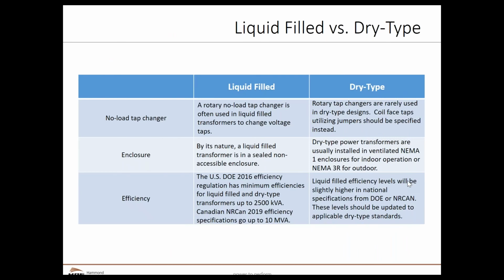So there's a couple things. We sometimes run into a situation where a specification says no load tap changers. This is where you can install a relatively simple mechanical tap changer in the actual oil that the transformer itself is submerged in. And by twisting a dial with a wrench or something like that, I can change the taps within the liquid. And there are some advantages to doing this. I can do this relatively inexpensively and easily because I'm not worried about arcing where I would be if the switch was just in air. And I also don't have to pull all those taps out with additional bushings through the transformer. So there are fewer points where that transformer can leak. Okay, this is not a bad solution for a liquid-filled transformer.